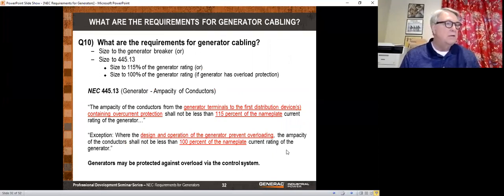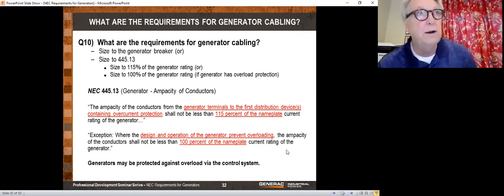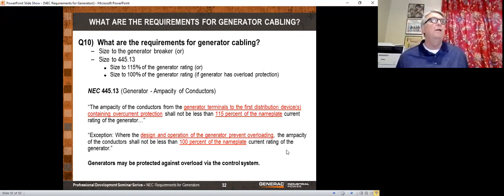Cabling. Now, this is an important one. I'm talking to people all the time about this because you go out there, you look at a generator, and let's say the generator full load amps is 340. It very well likely may have a 400 amp circuit breaker on there. So people would say, oh, I have to have 400 amp wire, because they're used to the fact that the wire has to be the same size as the circuit breaker because the circuit breaker protects that wire. Well, that's true in many cases. It is not true for a generator.